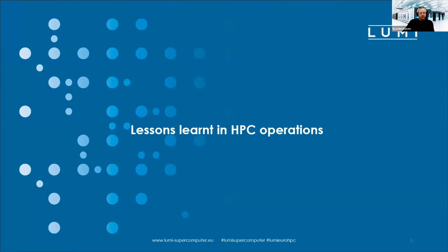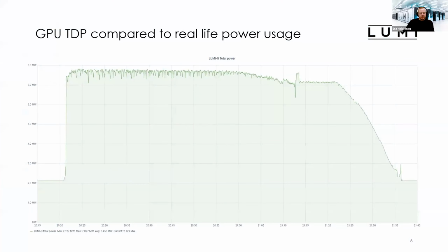So then, a couple of lessons learned about HPC operations. This is the latest HPL run in our GPU partition from this fall, which was actually submitted to the TOP500 list. This is a 1 second interval measured for the full GPU partition, and as you can see, the maximum power usage during the HPL was a little bit less than 8 megawatts, so it's quite small at the bottom of the picture, 7.8 megawatts of maximum power during the HPL run.